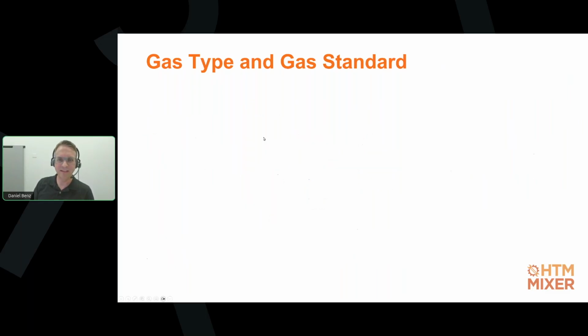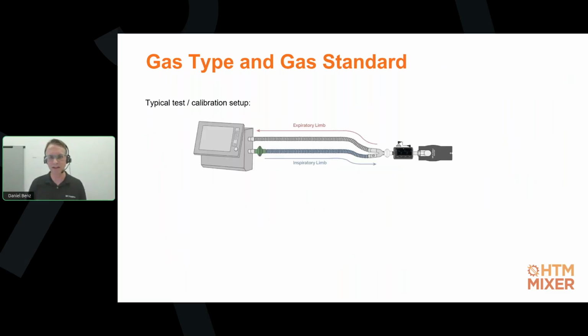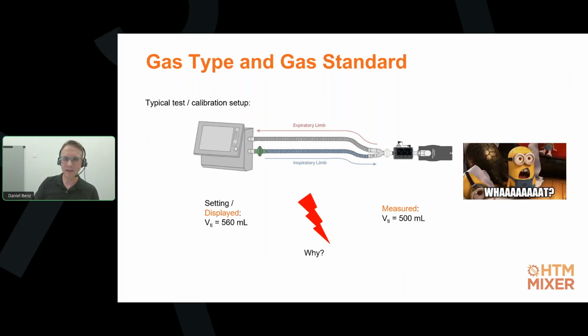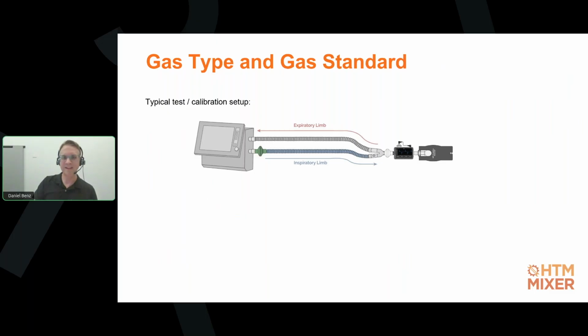Well, when we test such a ventilator with our gas flow analyzer, the setup typically looks different, more like what we can see on this slide. In such a situation, it can easily happen that we have a setting on our ventilator for tidal volume of 560 milliliters, but with our gas flow analyzer, we just measure 500 milliliters. So how can that be? Well, assuming that the ventilator setting is using the gas standard BTPS means that it is going to under-deliver in volume, as we have learned earlier.